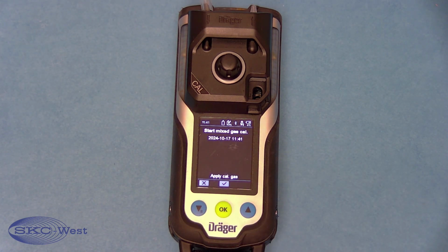hit OK. We want to make sure that we set up our regulator again to the calibration adapter with the tubing on the left hand side with the arrow pointing down. When we're ready to apply gas, we flow the gas and we press OK on the monitor. A calibration takes a little bit more time than a bump test, so give it approximately a minute to have everything stabilize. You will start seeing the green checks on the right hand side of each sensor. And once you get all 4 green checks, you can stop flowing your gas and hit the OK button on the monitor.